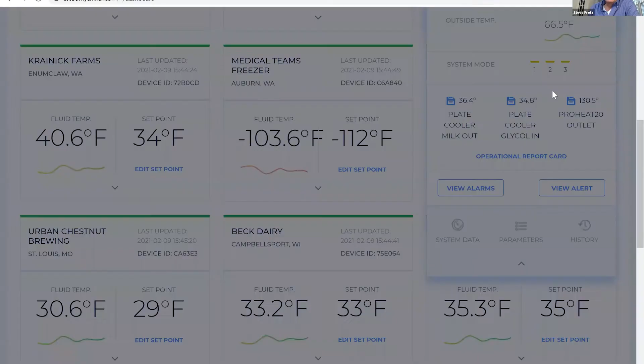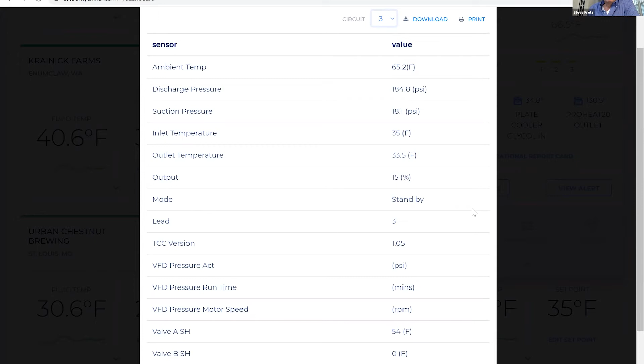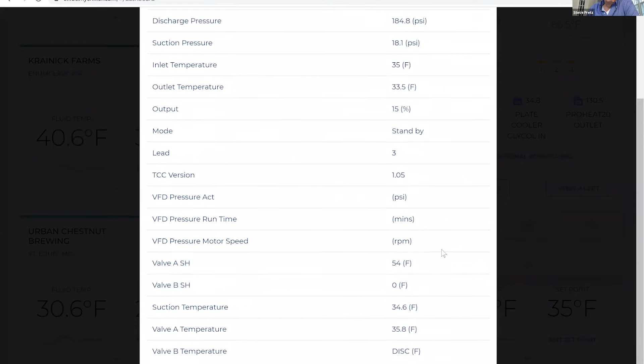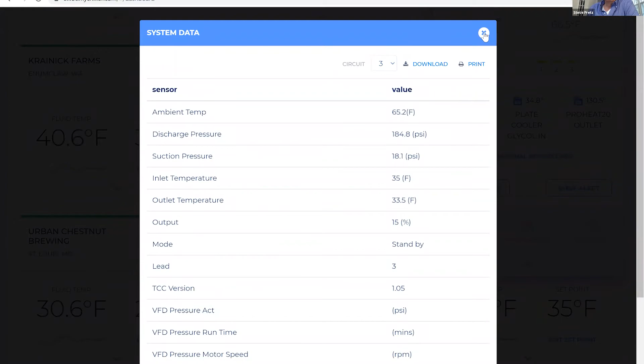Down here at the bottom, we're going to deal more deeply in tomorrow, or pardon me, on Thursday with Damon's session. But a high overview of this system data is, as the name describes it, it's the data of the system. Again, ambient temperature, you can look at it per circuit. If we want to remember, this one had 3 circuits. So we can look at suction pressure, inlet temperature, things that as a dairy producer may not be that relevant in your day-to-day activity. But when we looked at it earlier, unit number 3 was the one that was operating. So if your service provider says, hey, what's the discharge pressure? You can look at that and give him an exact reading in real time. Right now it's 184 PSI. We're only using 15% of the output. Just very basic readings that would be important to any service provider in troubleshooting your system or getting you some help.